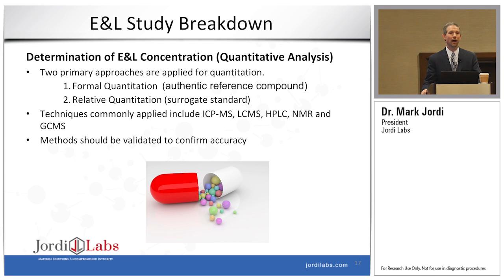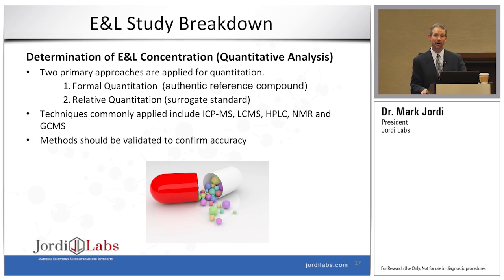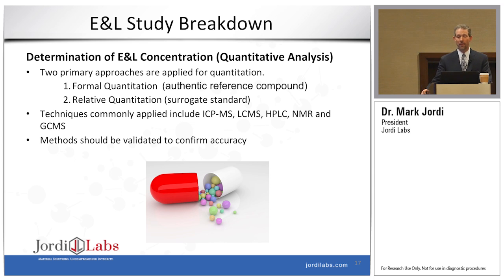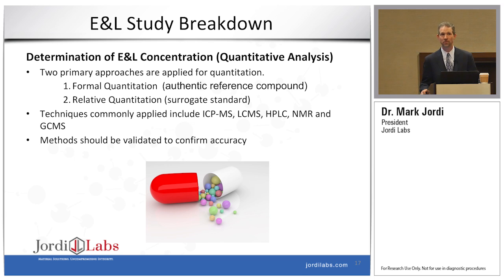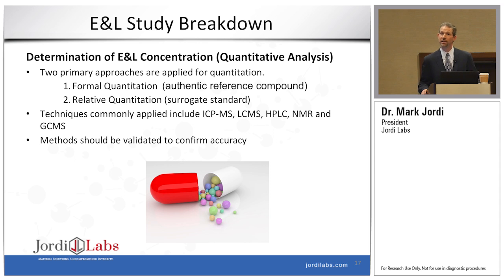Once we have identified what is present in the extractables and leachables profile, the next important step is to quantify it. This is an area I have a lot of passion for because I feel the way this is currently done in the industry is not very good, to be honest. There are two strategies that are widely applied: formal quantitation, which generally gives very good quantitative values, and relative quantitation, in which a surrogate standard is utilized and you get a relative value — and depending on which techniques you're using, that may or may not be appropriate.